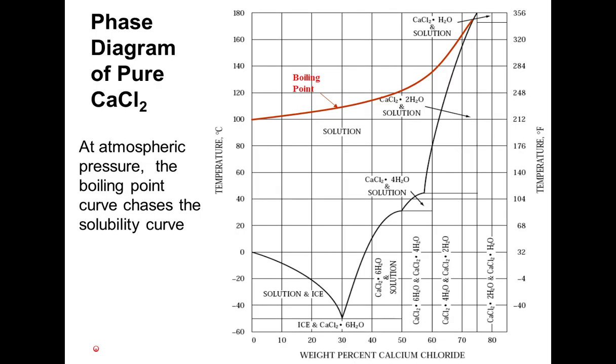Well, again, so what? This phase diagram for calcium chloride might help to explain what's going on. There's two lines on this diagram. First of all, on the vertical axis, we're looking at temperature. On the horizontal axis, we're looking at the weight percent of calcium chloride solution in water. And you can see a red line that's drawn on the chart, which is the boiling point curve for calcium chloride. So if you follow that red line and you look at any concentration of calcium chloride, you can look over on the left or the right, and you can see the temperature at which that solution will boil.